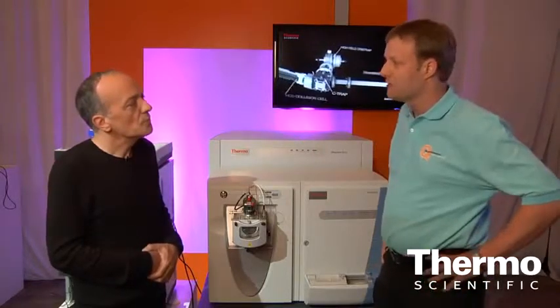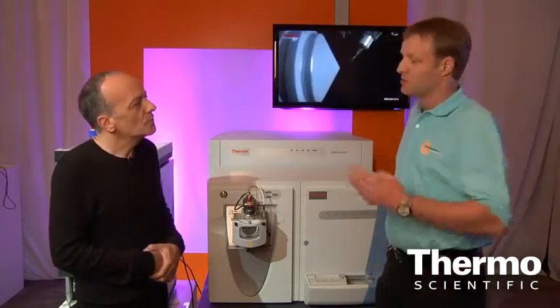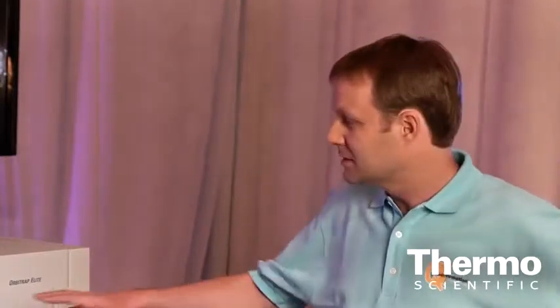Since the introduction in 2005, this is the first time we were able to implement this new analyzer in the system. That brings up the key features of the system in terms of resolving power and scan speed by a factor of four in total. That helps our customers solve questions where they run into complex samples and need speed in terms of productivity. The previous system had 60,000 resolving power at m/z 400 at 1 Hz. This system, using the high field Orbitrap plus advanced signal processing, brings it up to 240,000 resolving power — a fourfold increase.